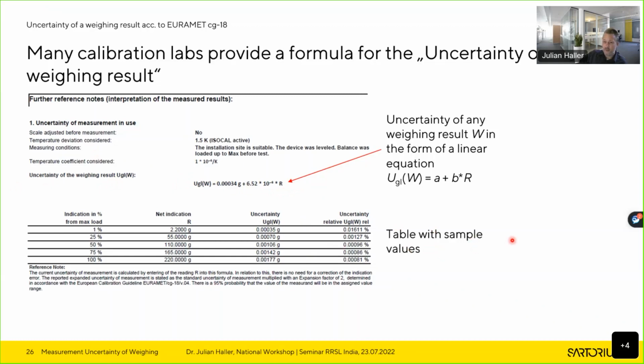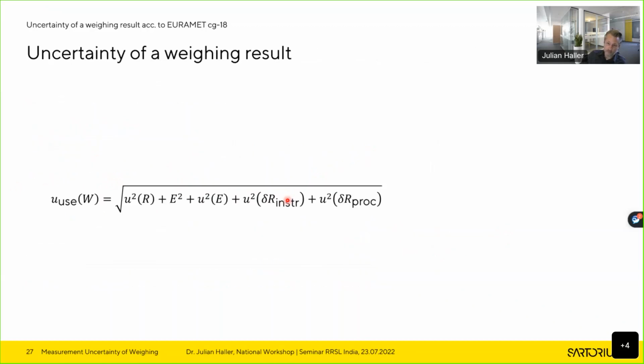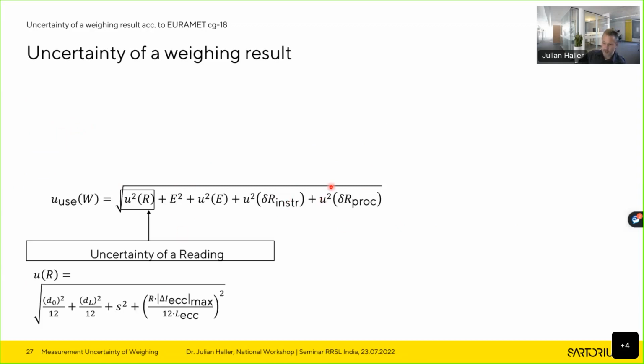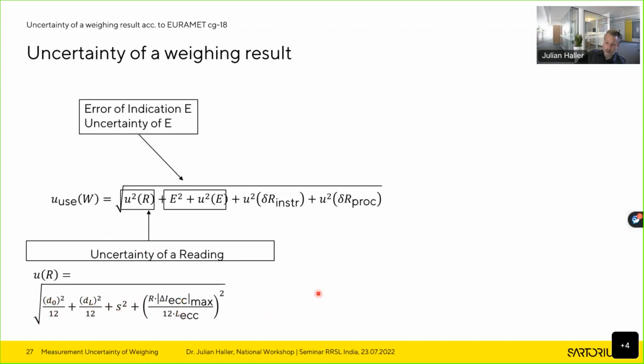And now let me just give you a brief overview of how this straight line equation is derived. The uncertainty of a weighing result of a user comprises several contributions. So of course you start with the uncertainty of a reading, and that is actually what we've seen before. If you as a user read the indication from a weighing instrument, you also have the contribution for rounding at 0, rounding at load, the standard deviation of repeatability, and possible eccentricity effects. The next part is that now, as the weighing instrument is calibrated, of course, you know it might have an error of indication, and this, as well as the uncertainty of the error of indication, have to be taken into account for the uncertainty of a weighing result.